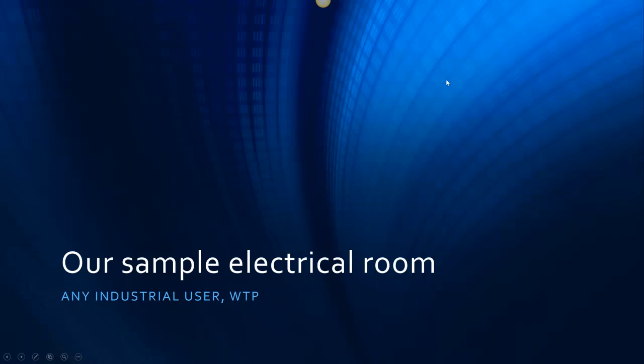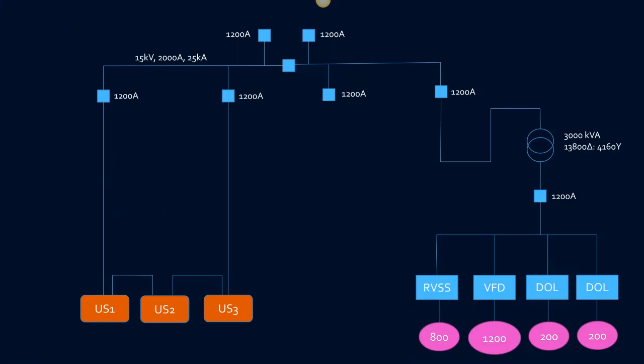Okay. So if we're going to talk about size and saving space, we're going to come up with a sample electrical room, and it's meant to model any medium-sized industrial facility, or maybe even a water treatment plant. And it's going to look like this. Your typical water treatment plant or industrial facility is going to have a lineup somewhere of medium voltage switchgear. They're going to be served from the utility at 12,470 or 13.8 or whatever. And they're going to have obviously this lineup of medium voltage switchgear.